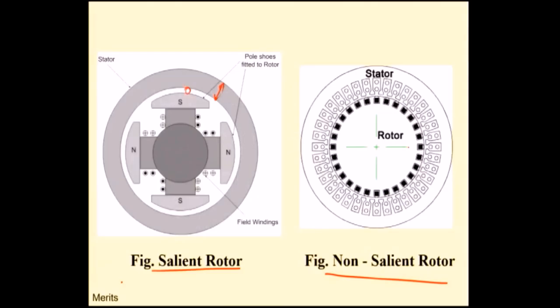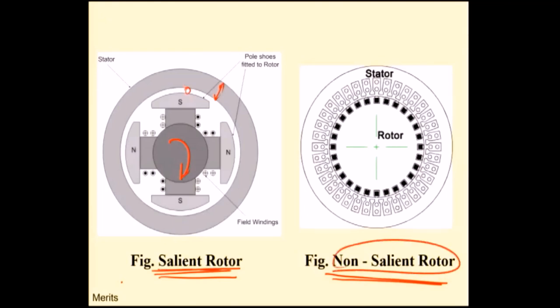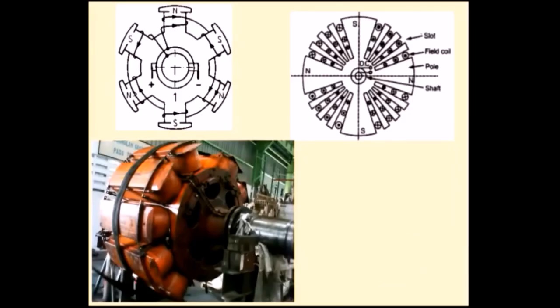In the salient pole rotor, the poles are projected, so if you rotate at high speed it produces more noise because the air gap is less. In non-salient pole rotors, we have noiseless operation. Also, the diameter of the salient rotor is more, which means the entire machine diameter is also more. The non-salient rotor has a smaller diameter and is of robust construction, whereas the salient pole rotor is not robust.